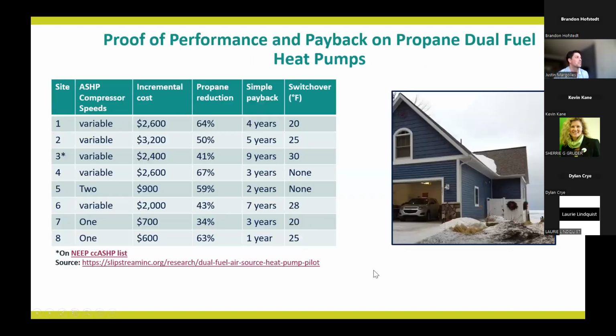In terms of proof of performance, here's info from a field study in Michigan. These were all market-installed systems, all dual fuel air source heat pumps sized for cooling. Compressor speeds varied, some 1 or 2 stage, some variable speed. All significantly reduced propane use and all paid back. The switchover temperature varied from 20 to 30 degrees; a couple labeled 'none' just had algorithms that switched when the heat pump couldn't keep up with the thermostat set point.